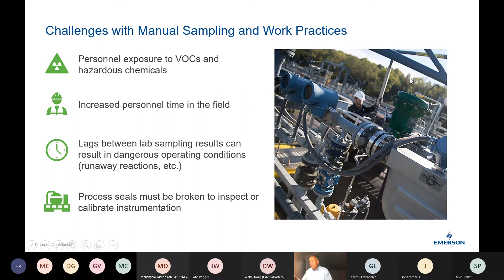So today, with modern multivariable instrumentation, a lot of these sampling tasks can be done in an automated sense, where a long time ago many of these measurements weren't sophisticated enough to do that. The kind of applications we're talking about are things like acid strength, concentrations, densities, viscosities, purity, that type of thing. There's a chart here. I won't go through every individual measurement, but many of these, things like Coriolis mass flow meters, can measure mass flow, density, temperature, and give you automated sampling data as a result.